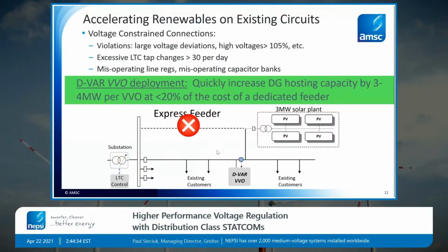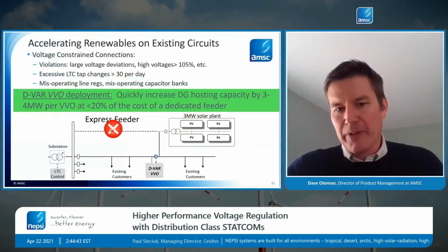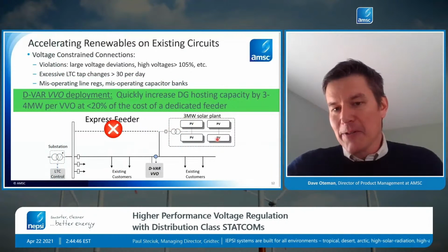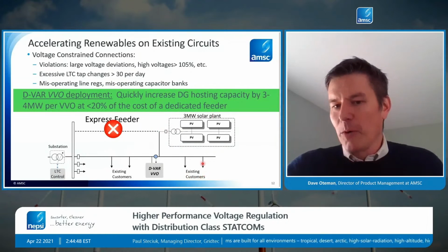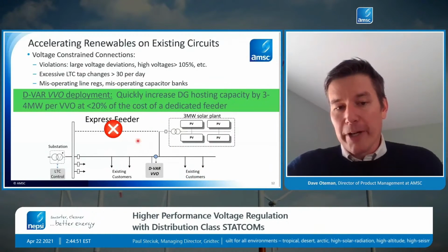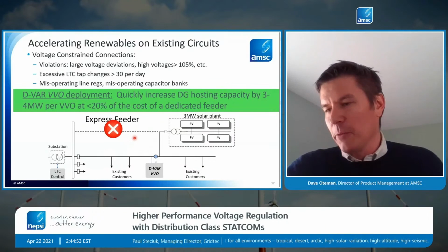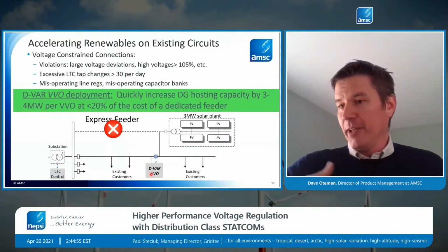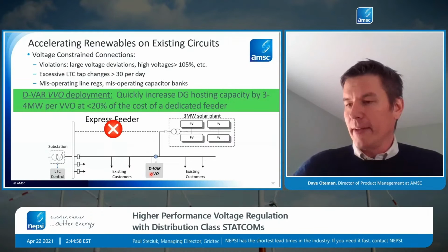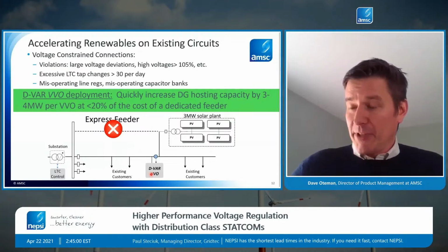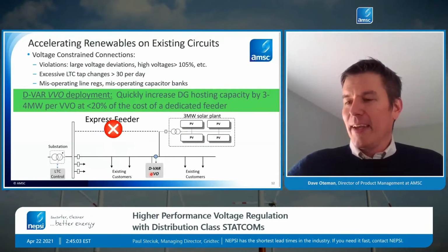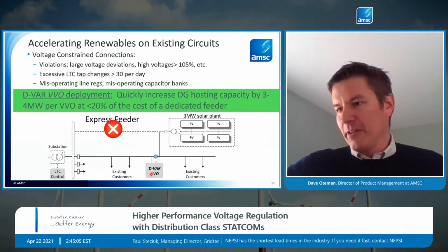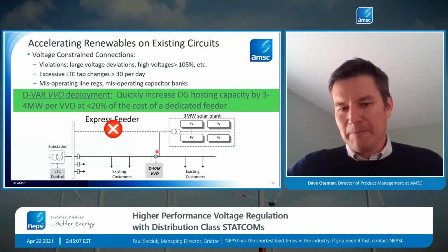One last comment here: utilities have historically offered wire-based upgrades. One technique is known as a dedicated feeder or express feeder, which allows the utility to protect customers from power quality issues. However, it's very expensive and time consuming. The STATCOM is able to achieve better power quality than a dedicated feeder, specifically when there are voltage violations, at a small fraction of the cost because it's just an apparatus.